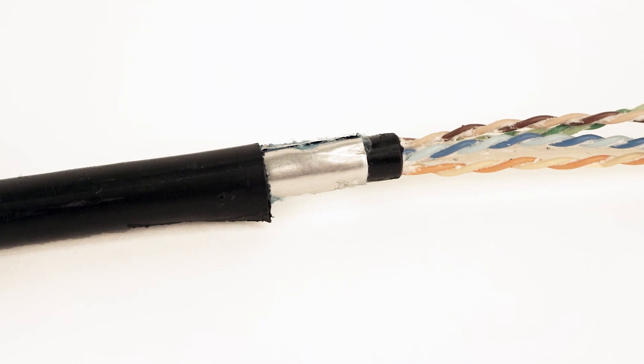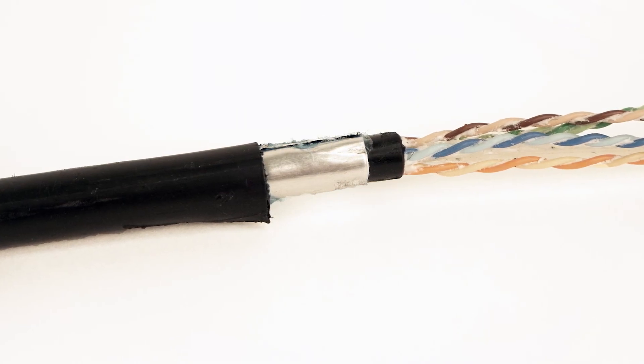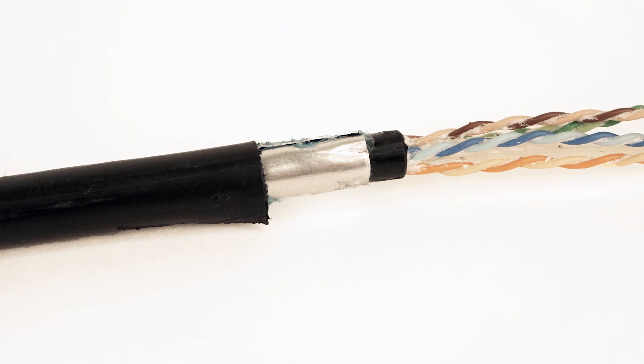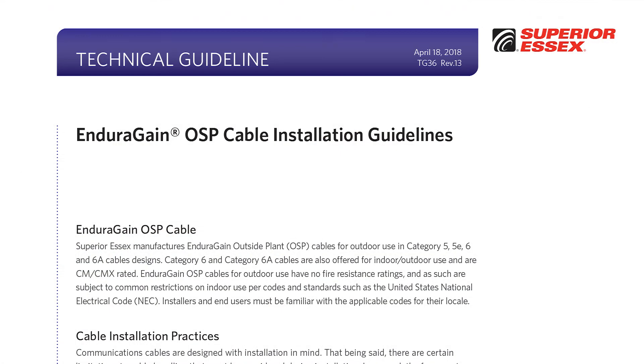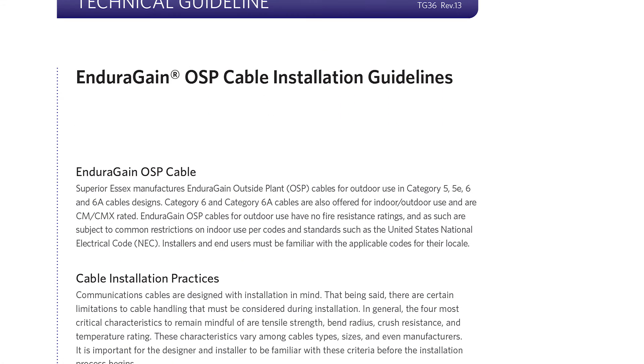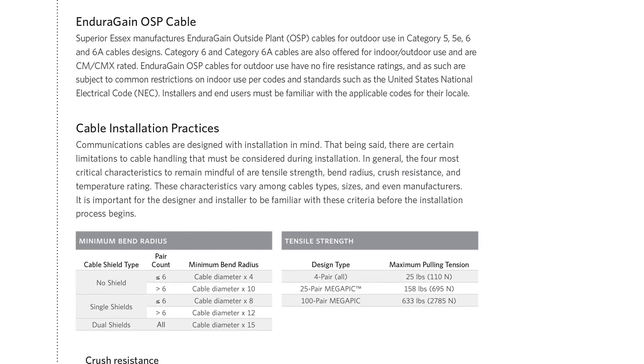It is important to note that the coating must be scraped from the shield to ensure a good ground if the hardware does not effectively penetrate the coating. Please see our Endura-Gain OSP cable installation guideline for additional details about this method.